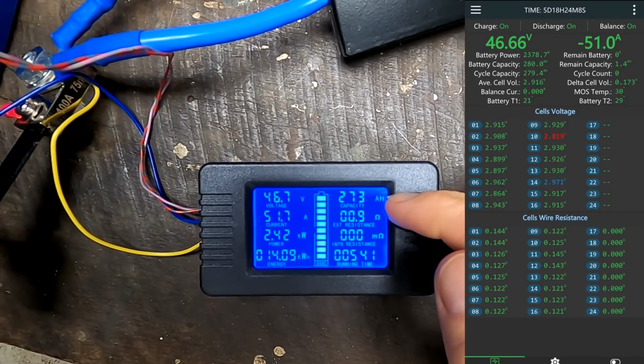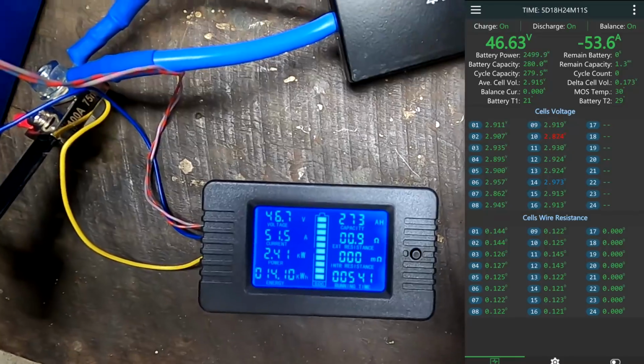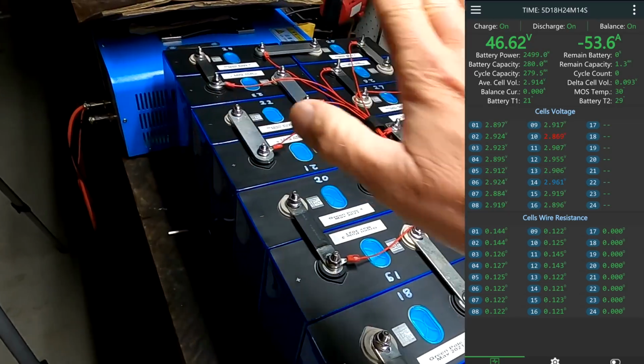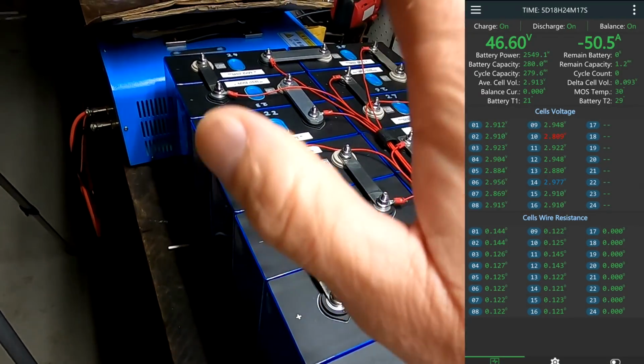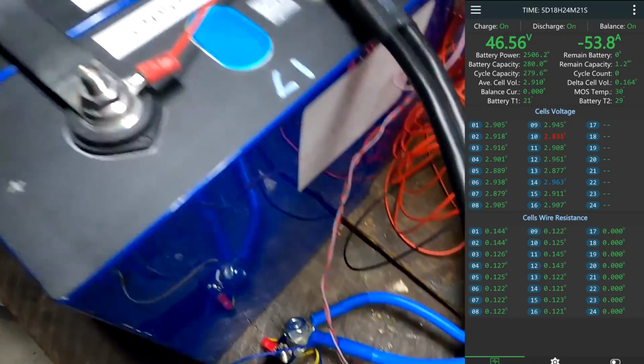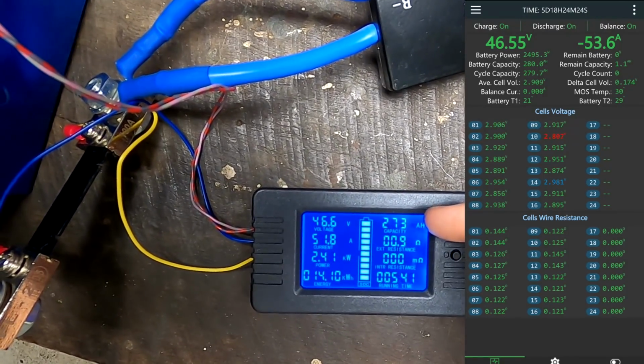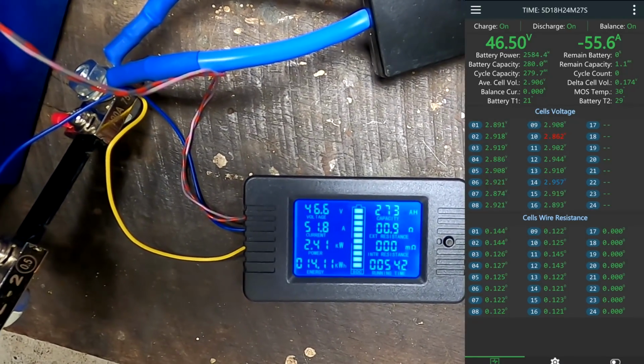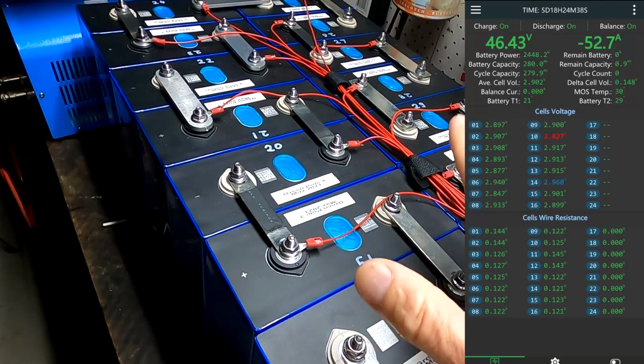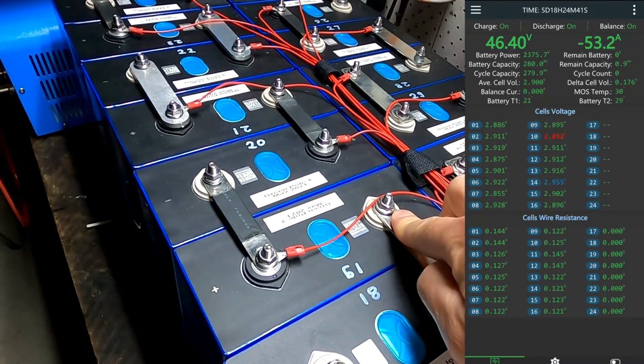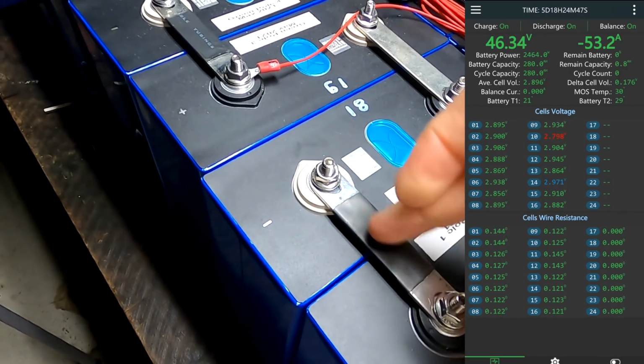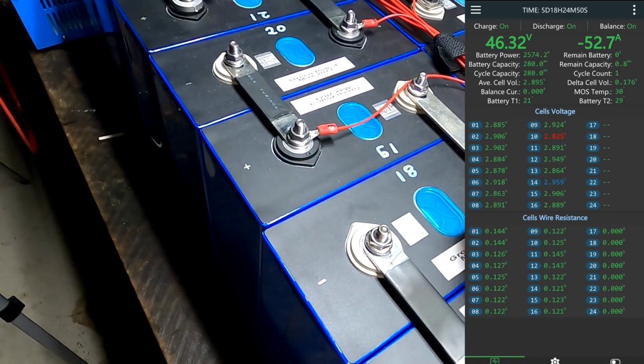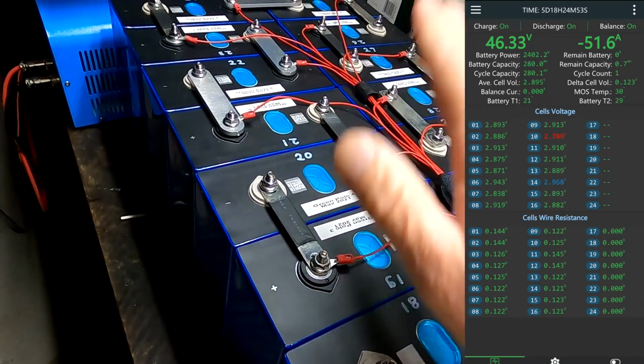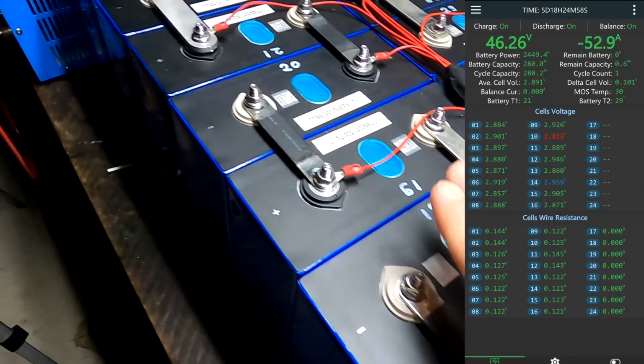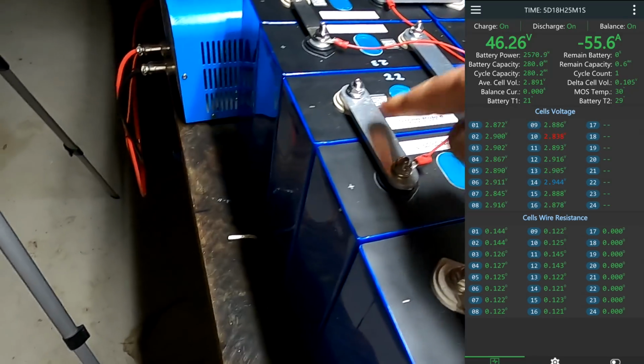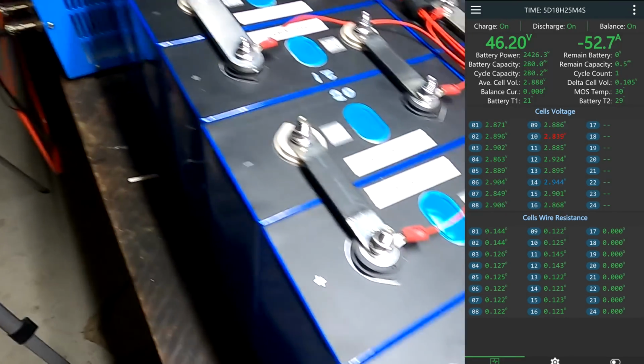Yeah, I don't think we will reach the 280 ampere hours here, but again, we have to see it's a 16S combination. It's a battery built out of 16 separate individual cells. And we can still pull 270 ampere hours out of them. That is very, very good. And this is also with totally unoptimized bus bars and connections to the terminals. These are just the old bus bars which came with the first delivery here, and they are scratched and marked and messed up already. So I just took them to connect the battery here. This will be all much better once we have the aluminium bus bars in place. They've got full contact around the whole terminal.